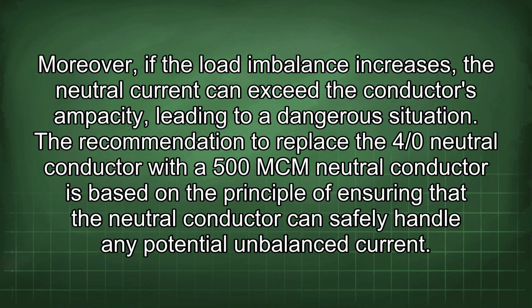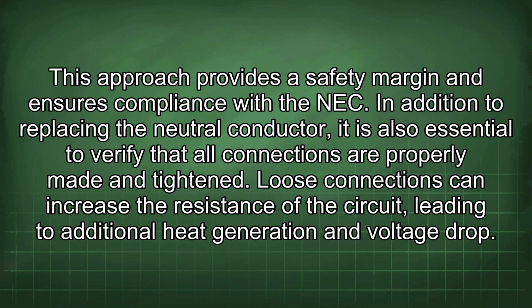The recommendation to replace the 4/0 neutral conductor with a 500 MCM neutral conductor is based on the principle of ensuring that the neutral conductor can safely handle any potential unbalanced current. This approach provides a safety margin and ensures compliance with the NEC.